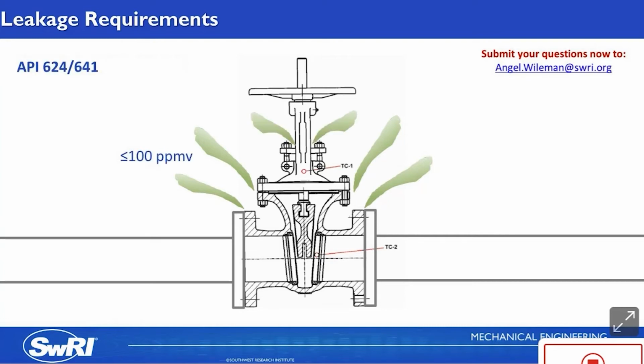For the API standards, the static and dynamic stem seal, body bonnet connection, and auxiliary valve body connections must all be sniffed, and the leakage requirement for all of these is 100 parts per million by volume. Again, those end flanges aren't required, but it's good practice so that you can make sure it's not affecting the readings that do matter.